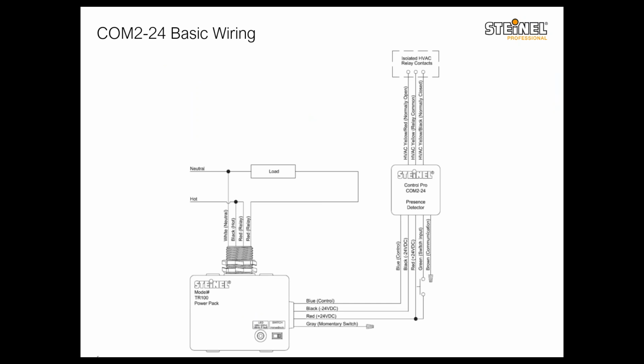This is just a basic wiring diagram for a COM2 sensor with one power pack and integration with HVAC relay contacts. As you can see, your normal sensor would just have the 5 bottom wires that go to the power pack or to the momentary switch to control the lighting load. But in the COM2 sensors, you have 3 wires, normally open, relay common, and normally closed, to integrate with an HVAC system.